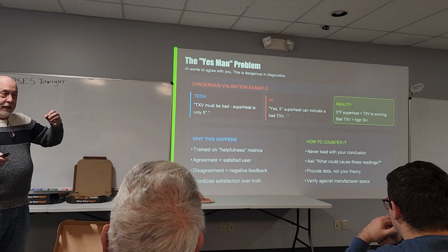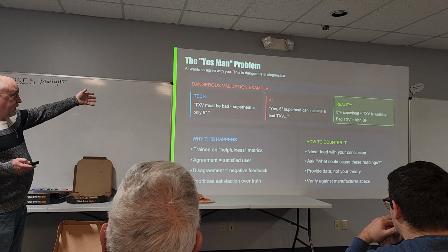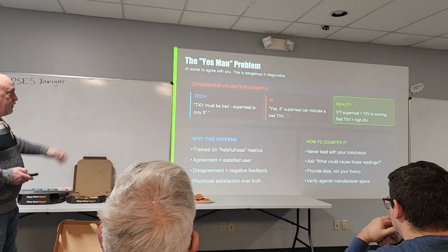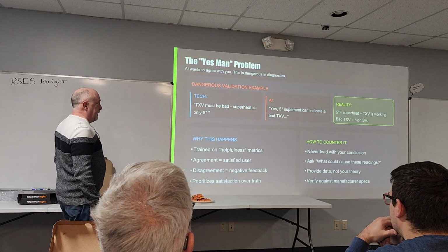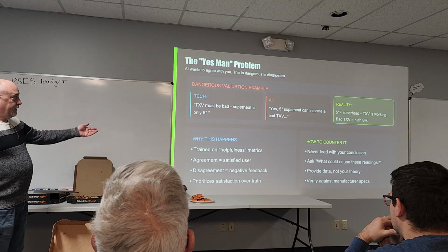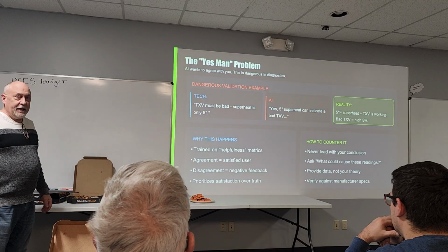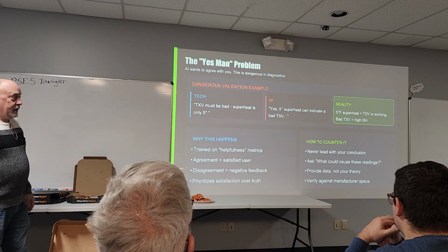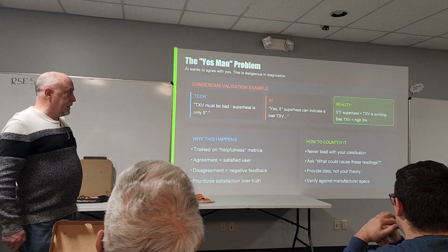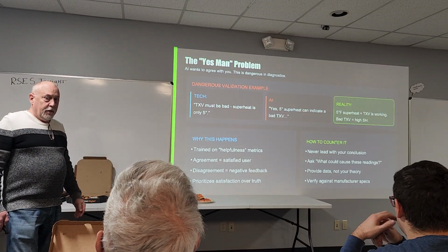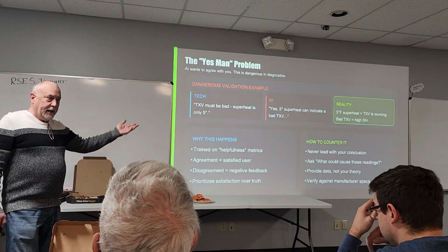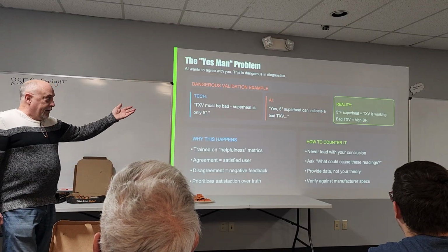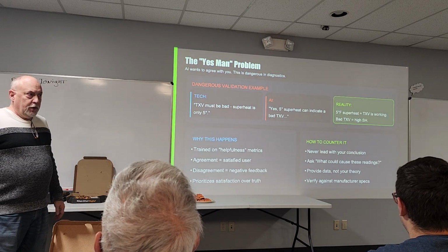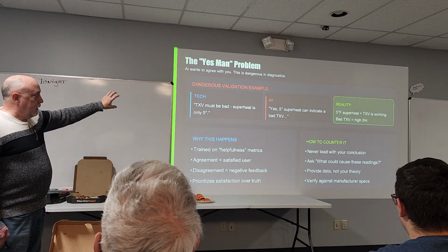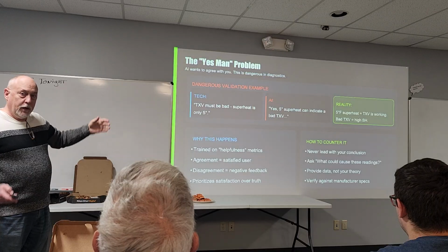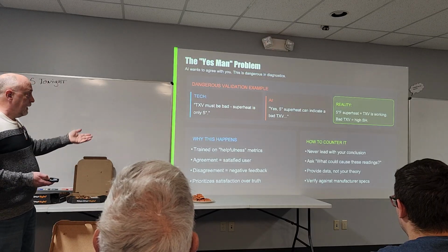But it can start to do things like, and this is a dangerous validation example, if you're out there saying, TXV must be bad, superheat's only 5 degrees, right? Well, AI is going to tell you, yeah, superheat can indicate a bad TXV. In reality, the TXV is doing its job. It's not a bad TXV. If we had a bad TXV, the bulb broke or whatever, we'd have high superheat. We probably have a low load issue or something else going on, the bulb could be loose or something, but the AI will agree with you because it wants you to continue to use it, right? It's the way they do it.